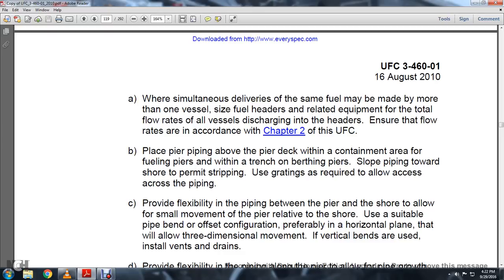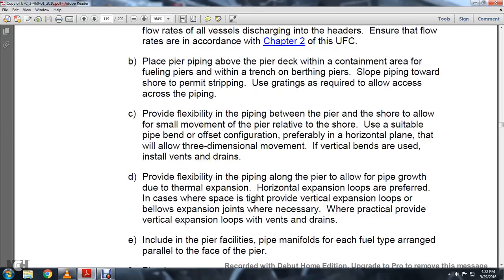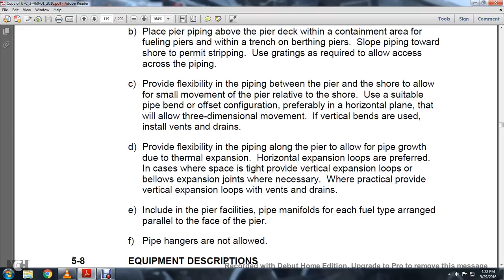Place pier piping above the pier deck within the containment area of the fuel piers, within a trench on the berthing piers. Slope piping toward the shore to permit stripping. Use gratings as required to allow access across the piping. C. Provide flexibility in the piping between the pier and the shore to allow small movement of the pier relative to the shore. Use suitable pipe offset configuration, preferably in the horizontal plane, which will allow three-dimensional movement. If vertical bends are used, install vents and drains.